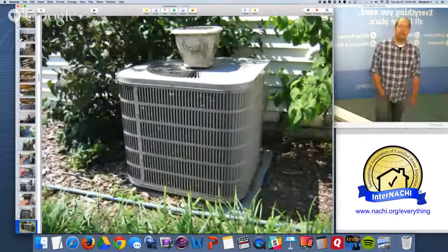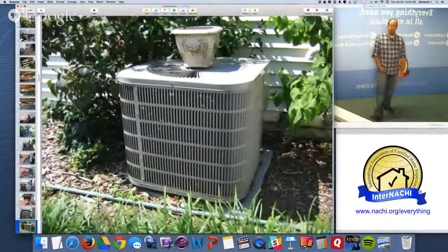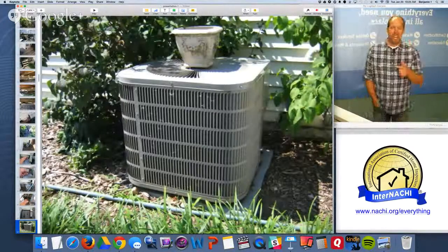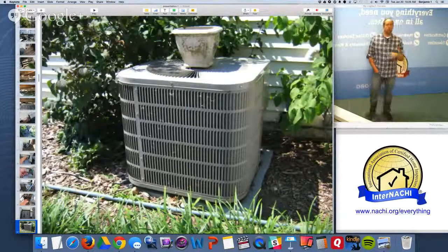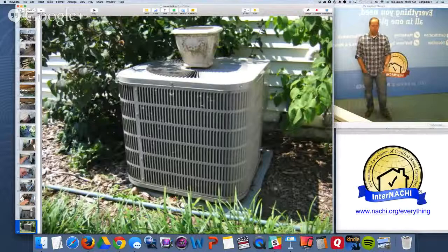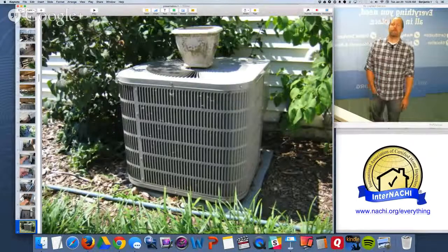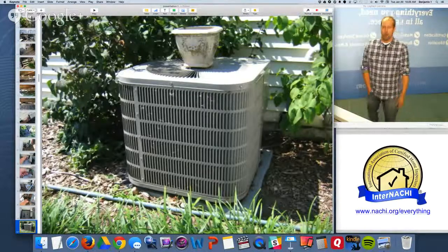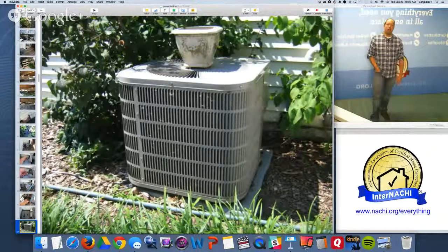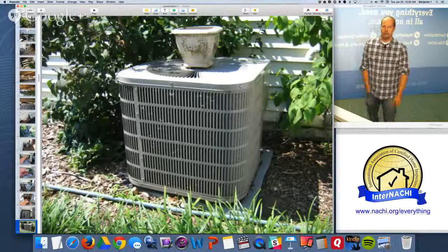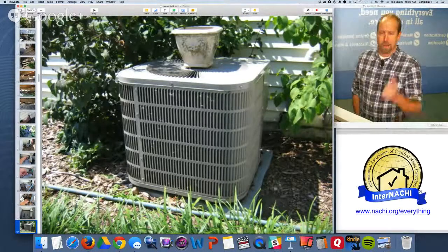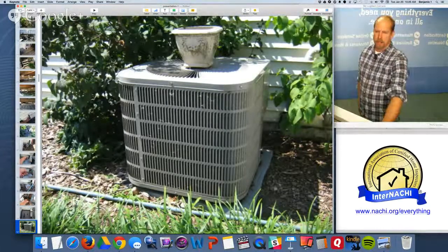There's the air conditioner — outdoor compressor/condenser unit, evaporator inside. I'm going to look for the age and condition, do a rule-of-thumb for sizing, just make sure nothing's way off — too big or too small. Most older homes with AC units have been sized too big for the home, which is a waste of energy. I look for the refrigerant lines — the liquid line, the suction line — and the electric shutoff disconnect.